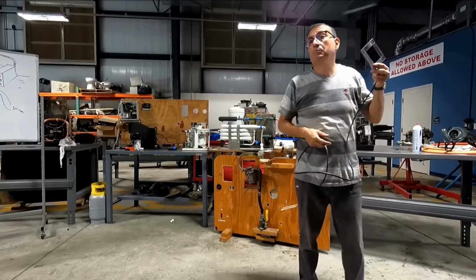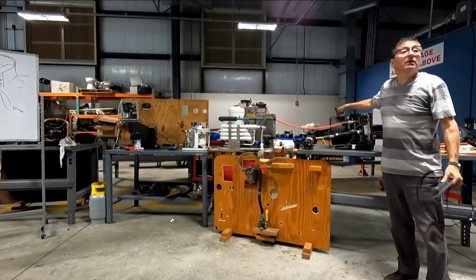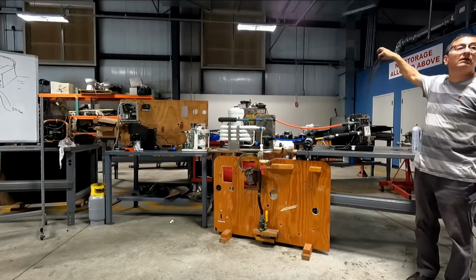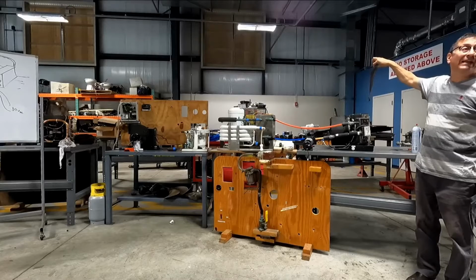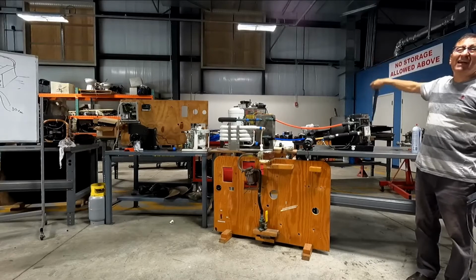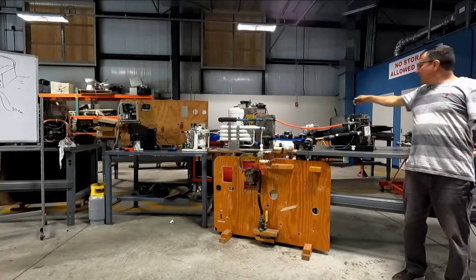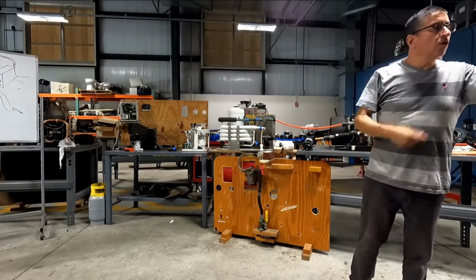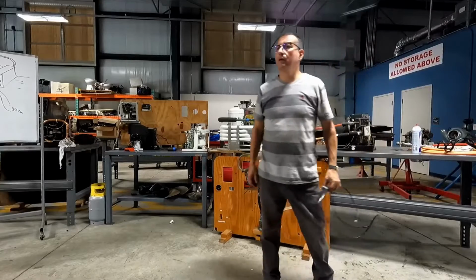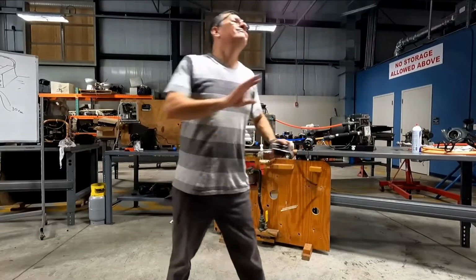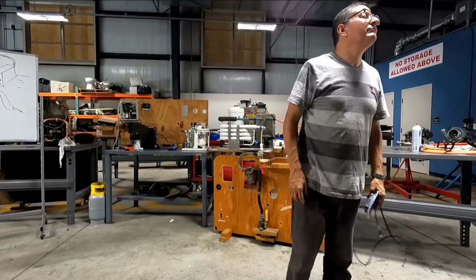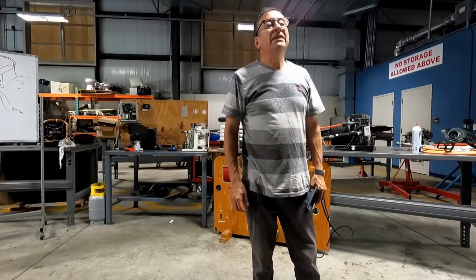Probably the blower is not blowing enough. Probably this is clogged. Oh, yeah. That's number one. This is clogged, the most common. And for that reason, the air is warm. But normally it's here or the filter. Because if you had a leak, all the system would be bad. Correct. You're going to see the leak because it has really good pressure in the system.